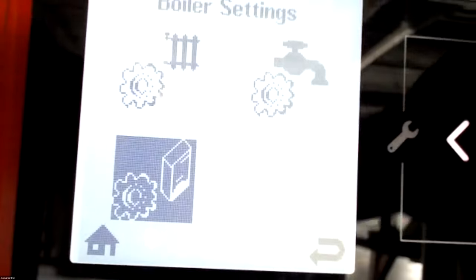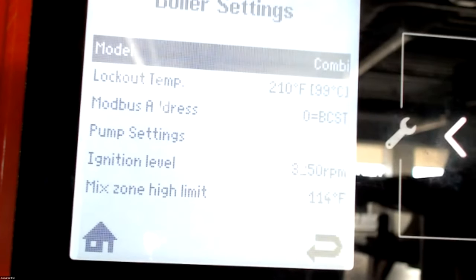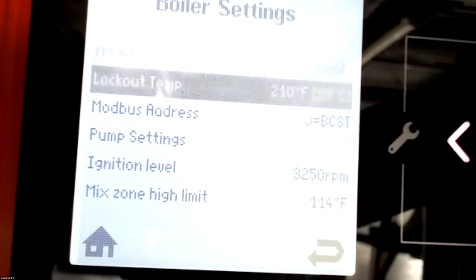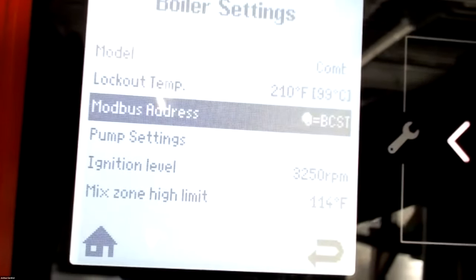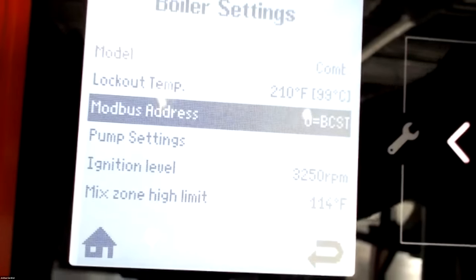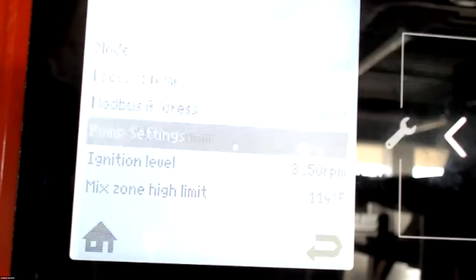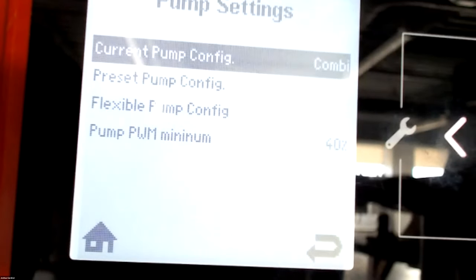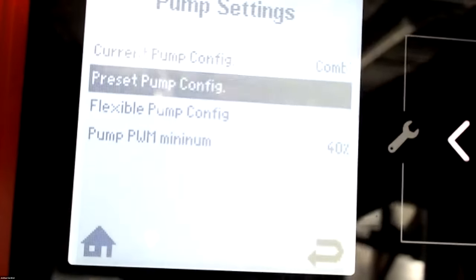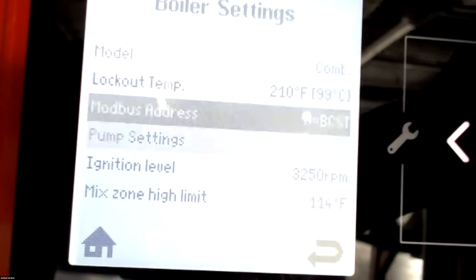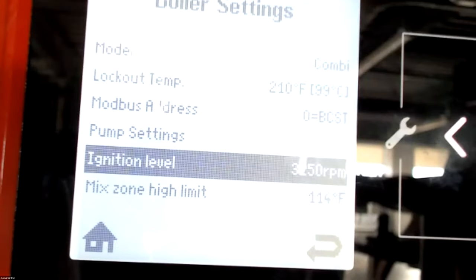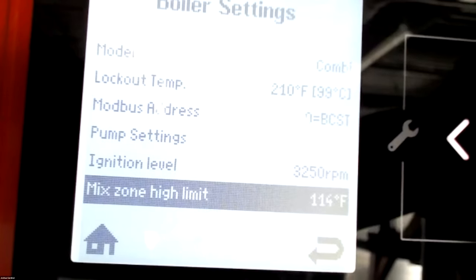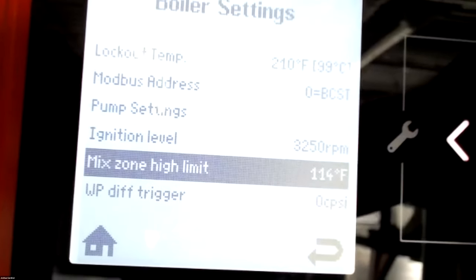So if we go down to our boiler settings, this is where it's going to show combi, our ultimate lockout temp, our Modbus address, where we enter that, and our pump settings. So if we want to, for some reason, change what pumps come on when CH1 calls, this is where we go in and adjust that. Our ignition level, if we're having some gas issues or venting issues we need to overcome, this is where we can adjust our ignition fan speeds. If we're using a mixed zone, we can adjust that temperature with this.